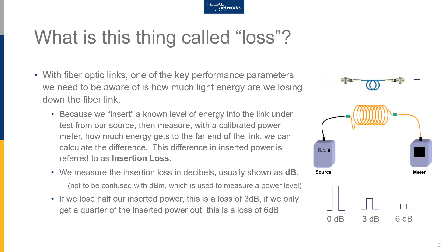Loss is a measure of how much light we are losing down a fiber optic link. As you can see from the top graphic, we put an amount of light into a link, and at the far end we get a reduced amount out. The difference between those light levels is the loss. We insert a known level of light energy into the link from our source, and measure at the far end — using a calibrated power meter — how much energy gets to the far end. The difference between the inserted power level and the received power level is the insertion loss or link loss.